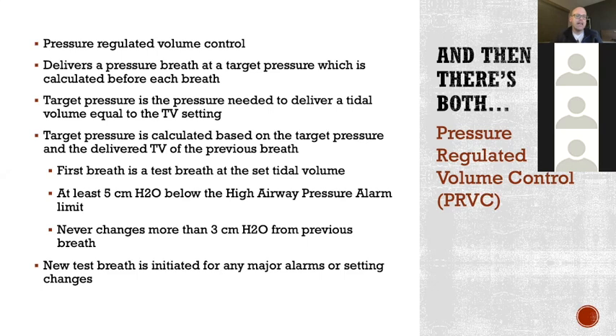And it's going to see how much pressure it took to deliver that breath. And let's say it took 23 of pressure. Then the next breath, it's going to deliver a pressure breath. And it's going to deliver 23 of pressure. And it's going to see how much volume it was. And if it's around that 500 cc mark that we had set, it's going to say, good, I'm going to keep going with this and give another breath at 23 of pressure.